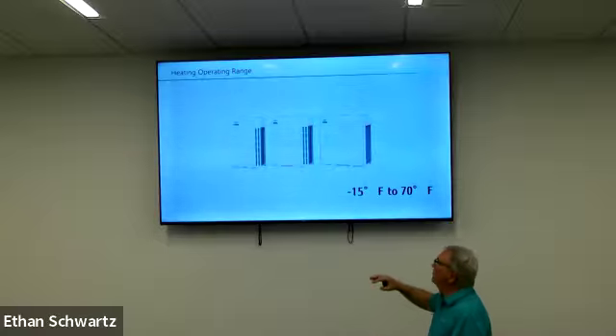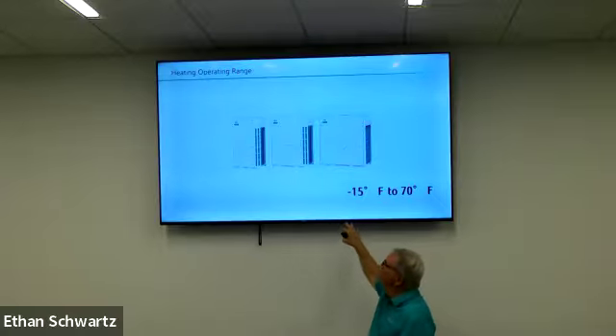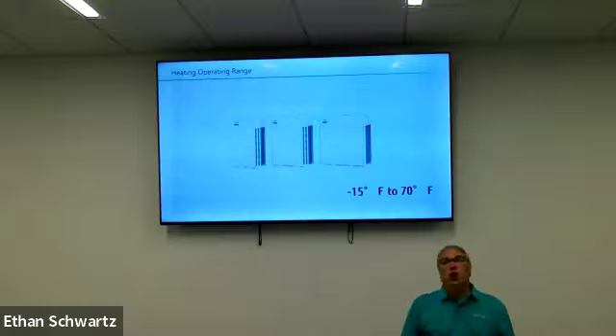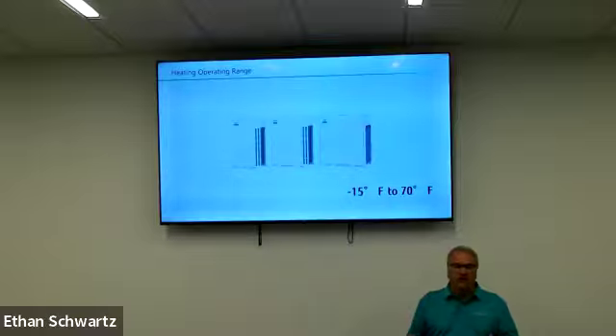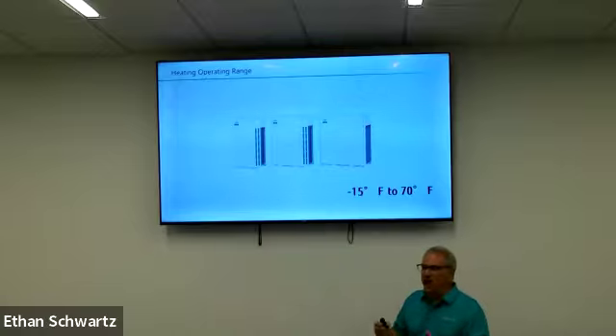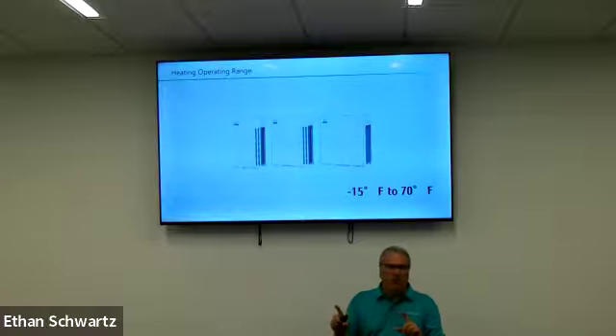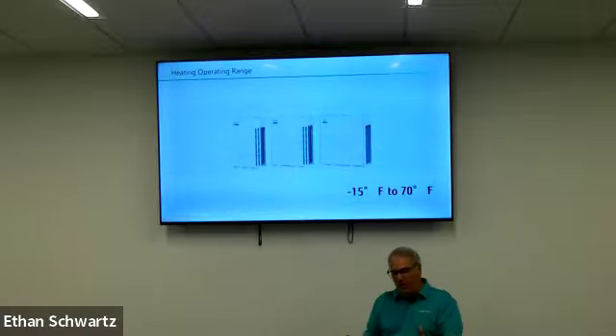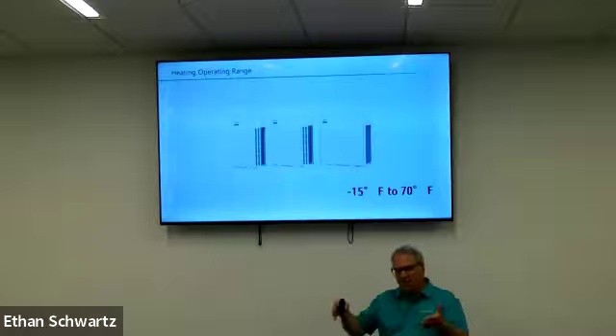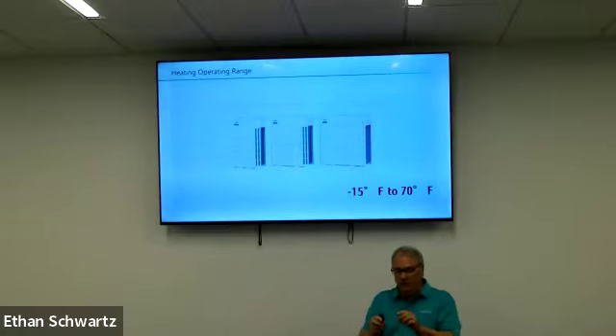I tell contractors, one of the most important things in low ambient heating products on heat pumps is don't distort the base pan. It may seem like, oh, that's just the base pan. It just supports the compressor and holds up the coil. No, our research and development engineers have spent time putting the holes in the proper location for how that coil is going to drain, so that it maintains the proper surface tension.